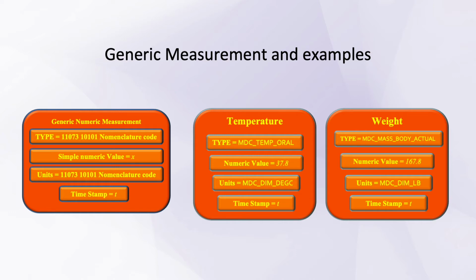Taking the temperature measurement using the generic numeric measurement object, the type now has a value: a code, MDC temp oral. This code tells you that this measurement, 37.8, is an oral temperature. 37.8 what? We look at the units, and the unit shows a code that, if you look it up in a dictionary, you'll see is degrees centigrade. Lastly, there's a timestamp, whatever it is.